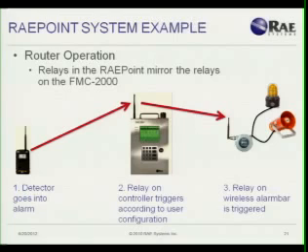In this example, we're using 1 horn and 1 light. But again, there's 5 relays inside of there. You can connect whatever you'd like to those relays. Our product, again, is intrinsically safe. When you start to connect other things, you need to make sure the devices you connect to it are intrinsically safe and that they're also certified for use, and the way you connect them through cabling or through conduit, those all have to be in compliance as well. But we do enable the ability to locate alarms and an alarm notification out in remote areas with a wireless connection. Okay, so that's the RAEPoint.